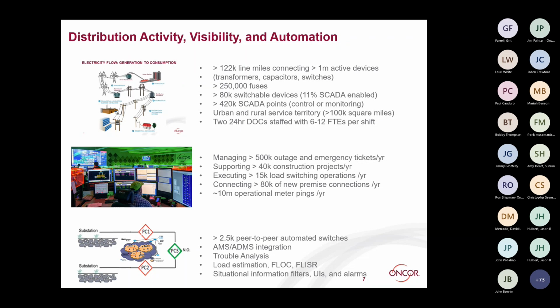So those devices may be miles away from where the customer lives that called in the outage. These kinds of algorithms and integrations exist in our distribution system. There are some acronyms here: fault location, automatically locating faults based on the measurements or information we get back. Same with automated isolation and switching, where the software automatically suggests how to respond to a power interruption. Those are all integrations that exist in modern distribution management systems.